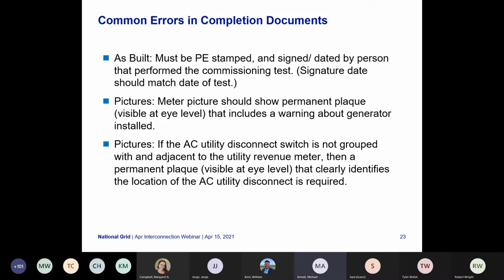We also will require photos for the AC utility disconnect. If it's not grouped adjacent to the utility revenue meter, we do need a permanent plaque visible at eye level that clearly identifies the location of the AC utility disconnect. Again, this is also for first responders as well as National Grid. If it's not right there, we need to know very quickly where it is located.